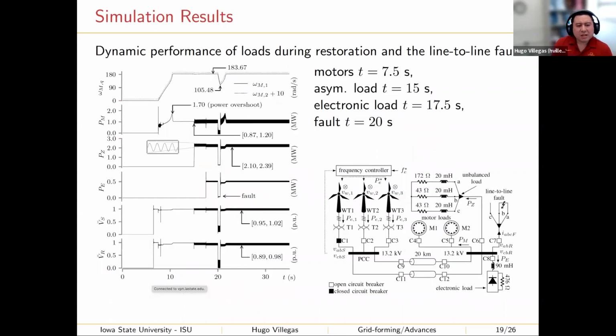All right, so the first challenge that we have to face is to start up motors. So we energize the motor, for example, at time t equals 7.5 seconds, and the motors start accelerating. There are two motors. Each motor is loaded with a 500 kilowatt pump. And then the energization was successful. I mean, we had enough currents from the turbines to energize these motors. In total, it was 1 megawatt. So how many wind turbines do we have here? We have 6 megawatt wind turbines.